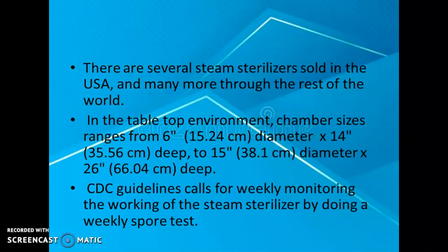In the tabletop environment, chamber sizes range from 6-inch diameter by 14 inches deep to 15 inches diameter by 26 deep. So there are different types of steam sterilizers. Here also CDC guidelines call for weekly monitoring of the working of the steam sterilizers by doing a weekly spore test.